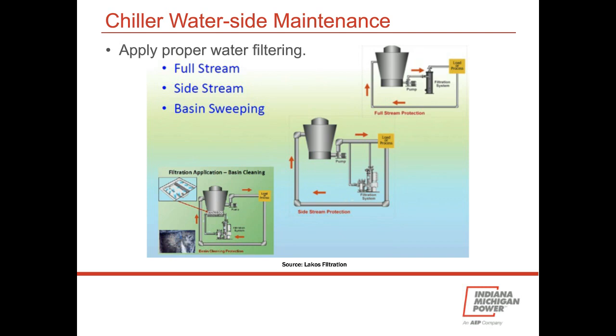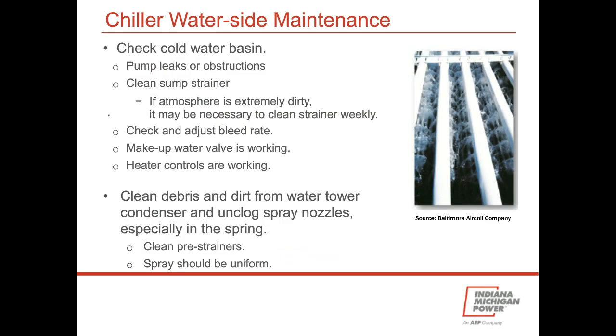I mentioned that cold water basin. Looking for any obstructions. We talked about keeping that strainer cleaned. Make sure the makeup water valve is working. And if you have metal, usually they're float type systems. If you have older metal floats, a lot of times those will corrode, and it can overflow, not drain, or it could use too much makeup water, and so you want to make sure that's working well as well. Here's a good example of the spray nozzles. You can see pretty much all of them are working. Looks like a pretty equal distribution pattern as well. That's what you want to see.